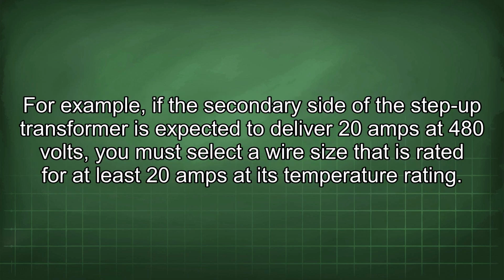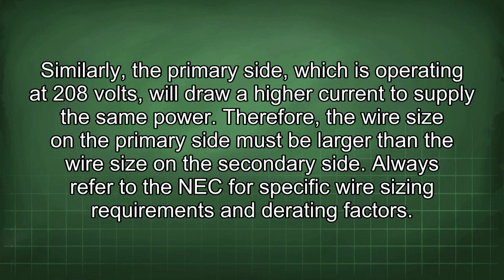For example, if the secondary side of the step-up transformer is expected to deliver 20 amps at 480 volts, you must select a wire size that is rated for at least 20 amps at its temperature rating. Similarly, the primary side, which is operating at 208 volts, will draw a higher current to supply the same power. Therefore, the wire size on the primary side must be larger than the wire size on the secondary side. Always refer to the NEC for specific wire sizing requirements and derating factors.